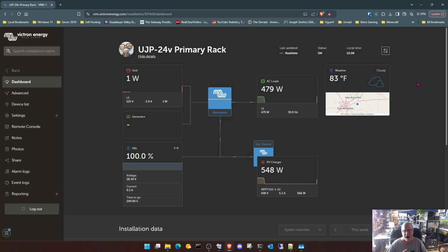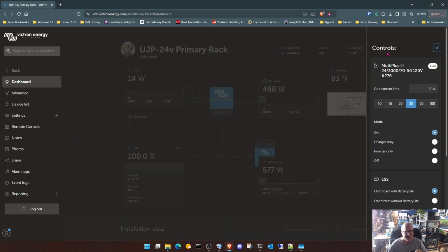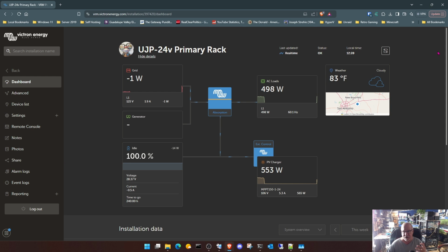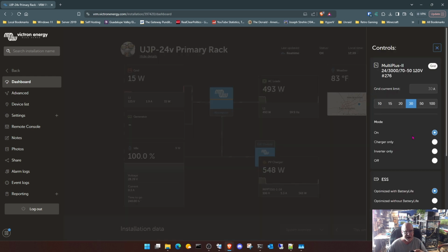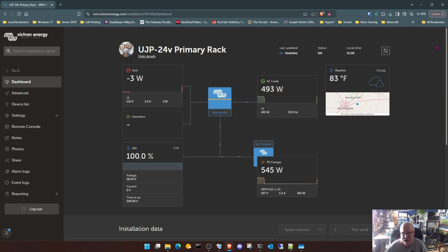And that's just a way to preserve the battery in case you have a critical event happen. You can also set this up to be optimized without battery life, and that'll take the battery down to 20%. And then you can see here I have it limited to using the grid to charge the battery at 30 amps. So I could, in theory, go up to 50 or 100 amps, but I don't think I can with this Multi Plus 2, this 24 volt unit.